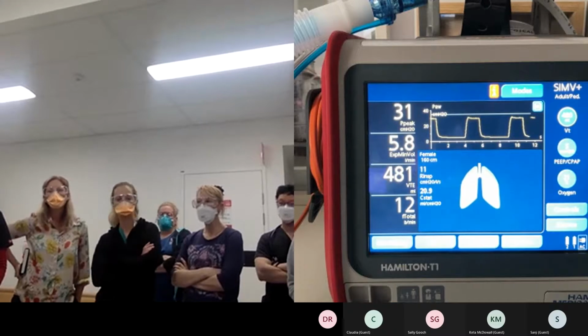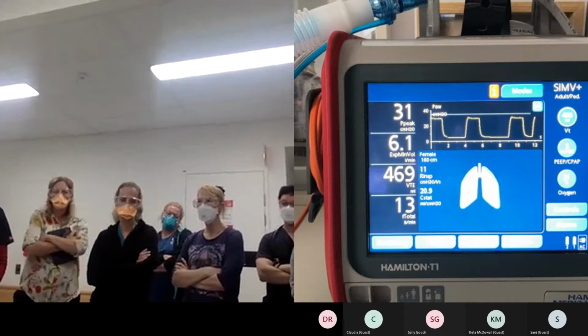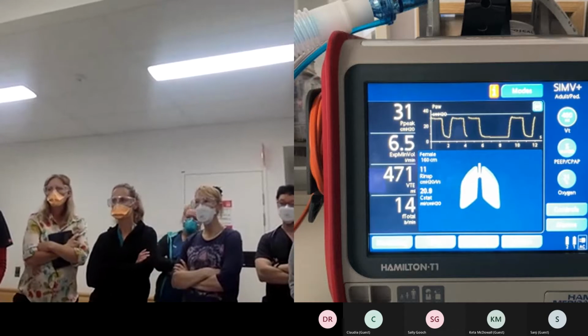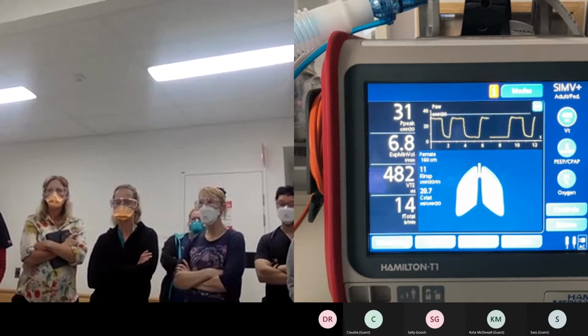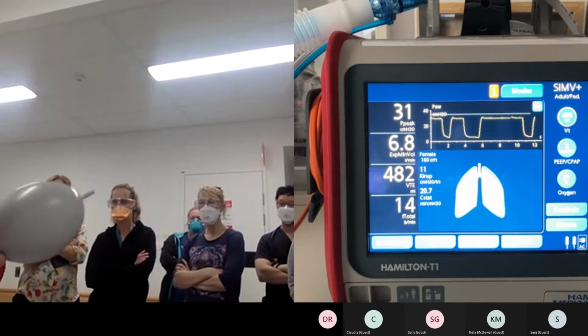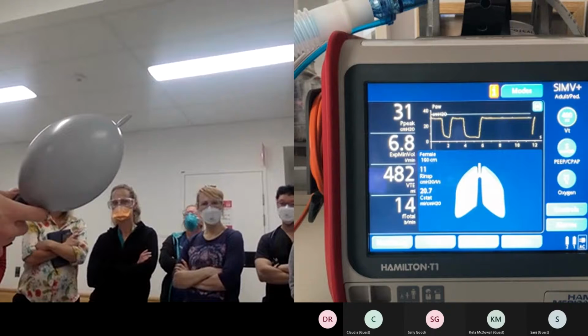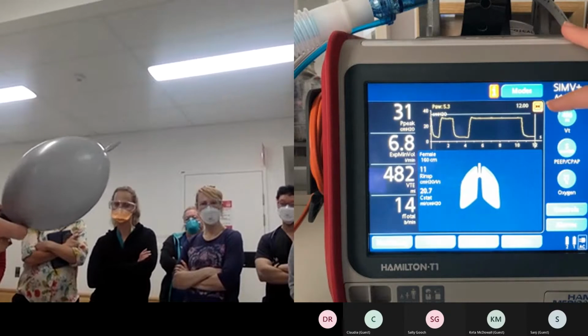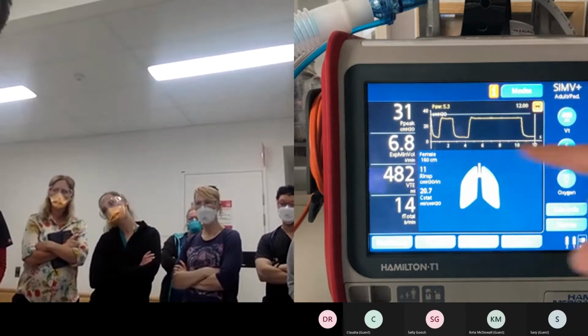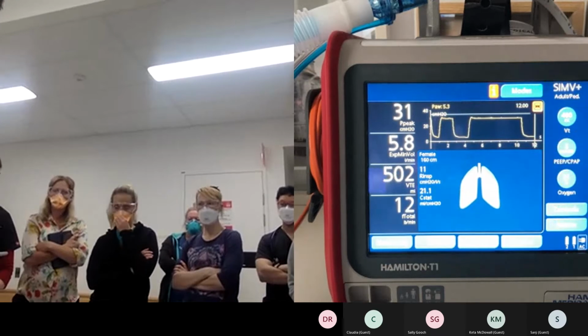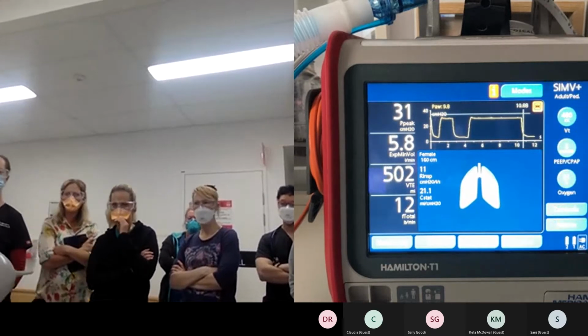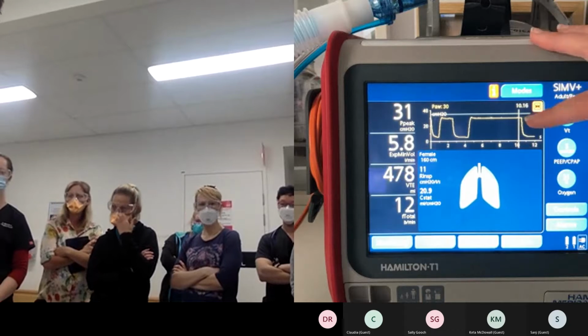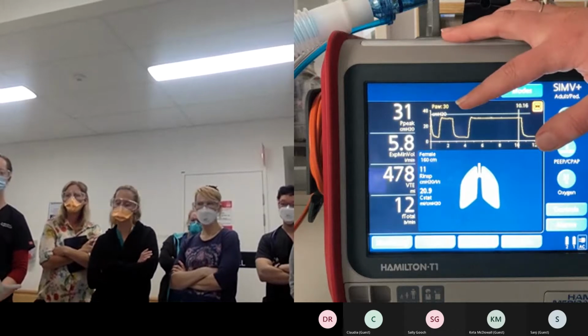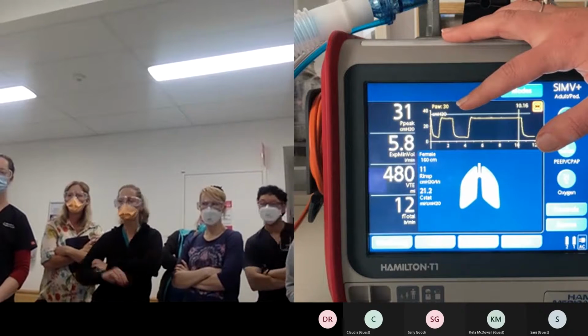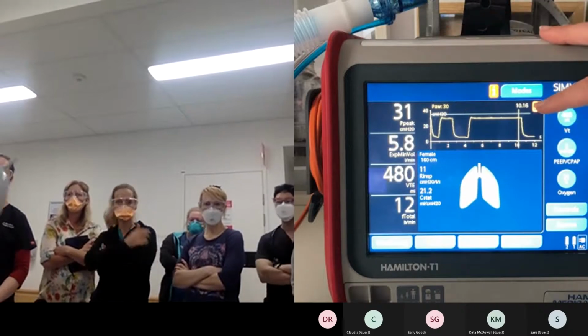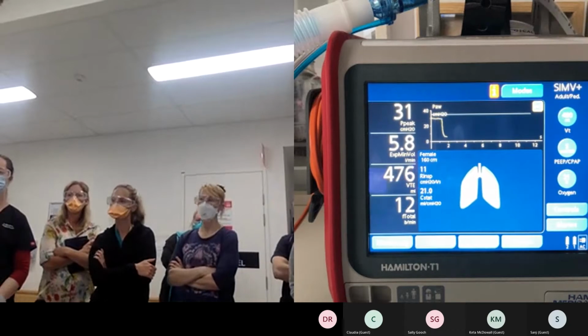The lung below it, when you touch on it lightly, delivers a manual breath. But if you press and hold on it, you can hold it for a few seconds, and then you've got the ability to use the pause button up the top. It pauses the screen. The ventilator still continues to deliver breaths, but you can come back and review what that plateau pressure was. Then you've got a number up in the corner letting you know. Okay. Unpause the screen, just press on it again.